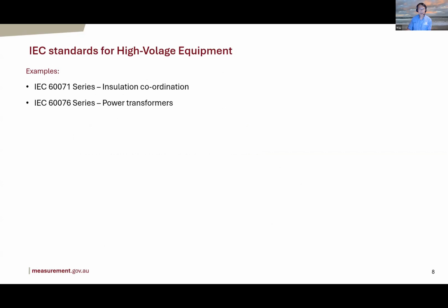So standard, also you have equipment standards where the HV testing specific requirements are specified, apart from those general standards. This standard is important because it specifies what's called insulation coordination. It specifies the voltage levels in the power systems. You can't just have arbitrary voltages. We know at home we have 230, the same in high voltage. You have only a number of voltages that can be used. So that standard is important in understanding the high voltage testing at the different levels.